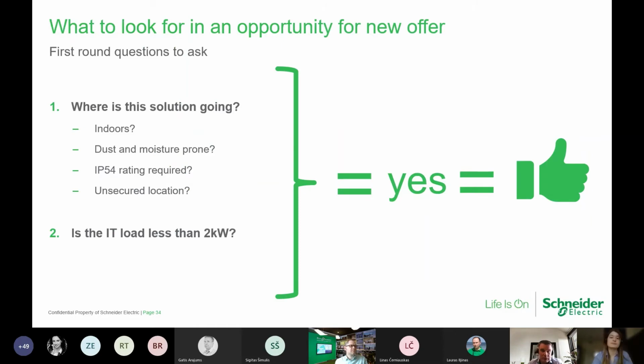So looking at the opportunities: if you or your customer need an indoor application for a micro data center, or to place IT gear indoors where the environment is dusty or moisture-prone, requiring IP54 rating, or in an unsecured location, and if the IT load is below 2 kilowatts, then you're good to go. You can contact your Schneider representative and ask for a quote for this kind of micro data center.